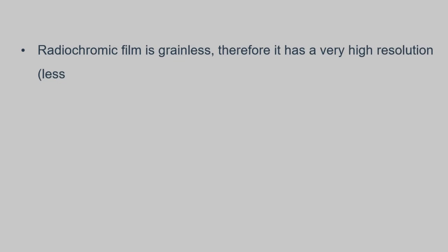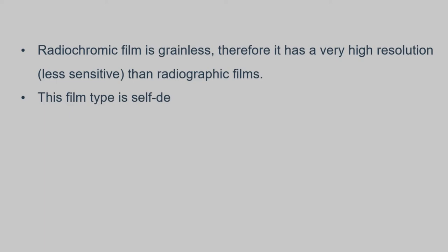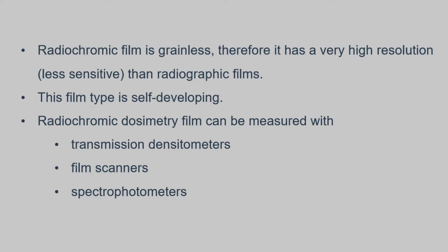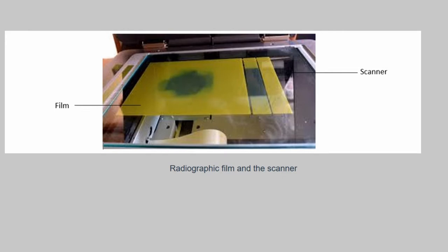Radiochromic film is grainless, therefore it has very high resolution compared to radiographic film. This film is self-developing, so it does not require developer nor fixer. Radiochromic dosimetry film can be measured using a transmission densitometer, film scanner, and spectrophotometer. This image shows the radiographic film and the scanner. The blue-greenish part is the exposed part of the film.